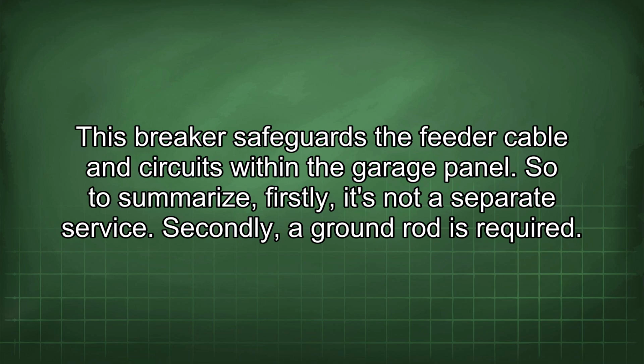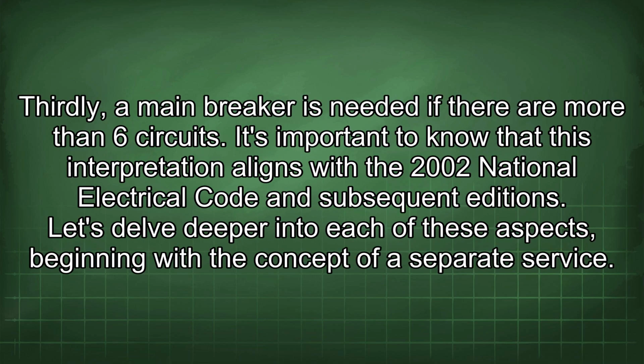So to summarize, firstly, it's not a separate service. Secondly, a ground rod is required. Thirdly, a main breaker is needed if there are more than 6 circuits. It's important to know that this interpretation aligns with the 2002 National Electrical Code and subsequent editions. Let's delve deeper into each of these aspects, beginning with the concept of a separate service.